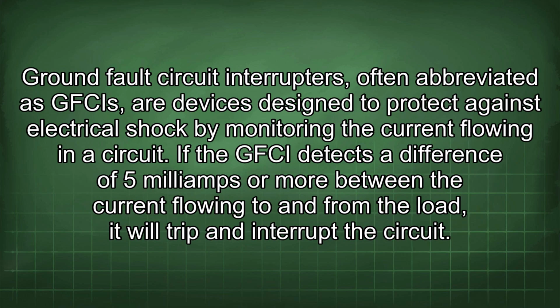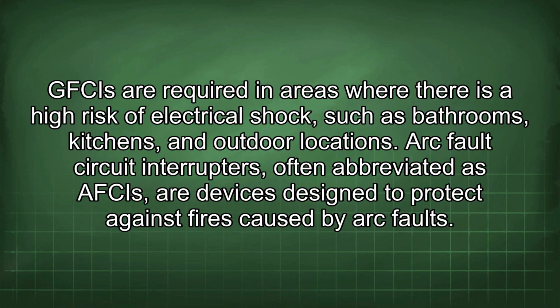Ground fault circuit interrupters, often abbreviated as GFCIs, are devices designed to protect against electrical shock by monitoring the current flowing in a circuit. If the GFCI detects a difference of 5 mA or more between the current flowing to and from the load, it will trip and interrupt the circuit. GFCIs are required in areas where there is a high risk of electrical shock, such as bathrooms, kitchens, and outdoor locations.